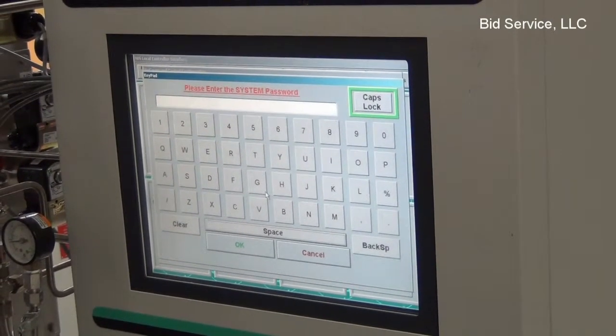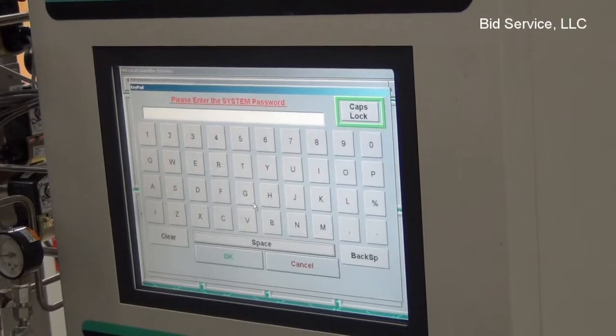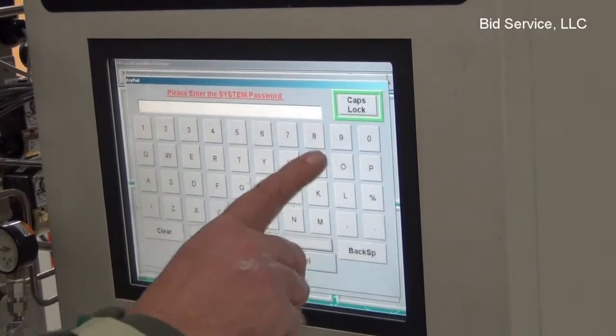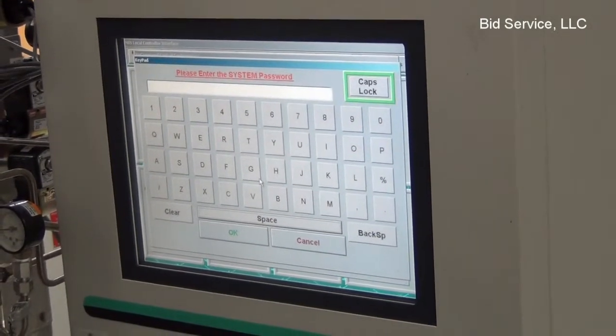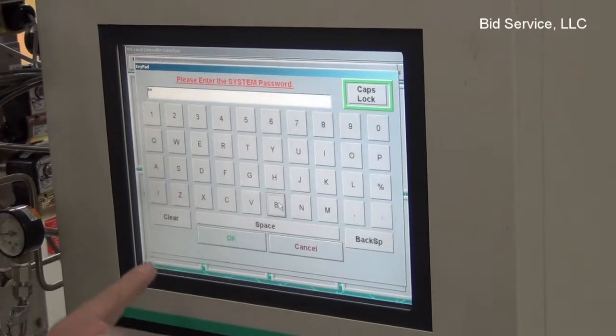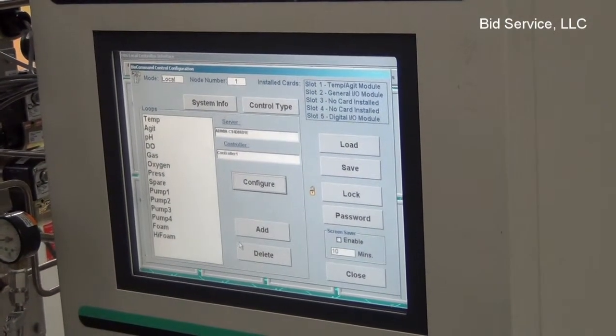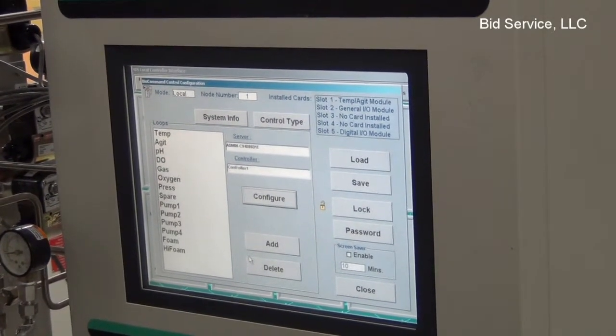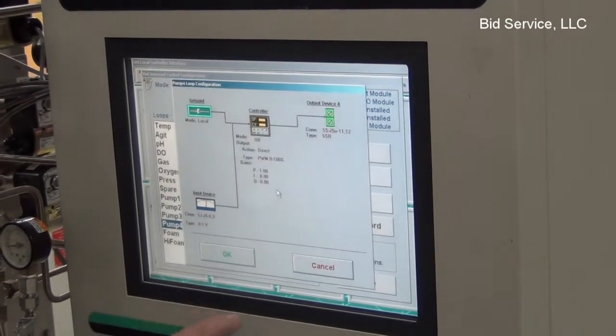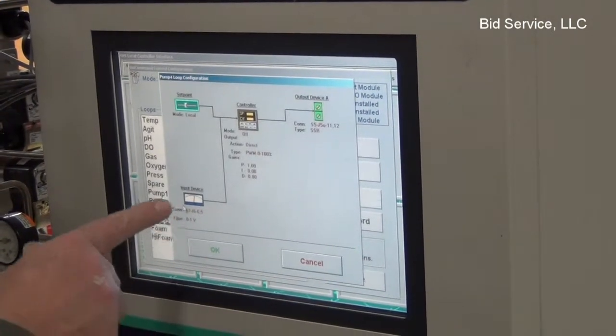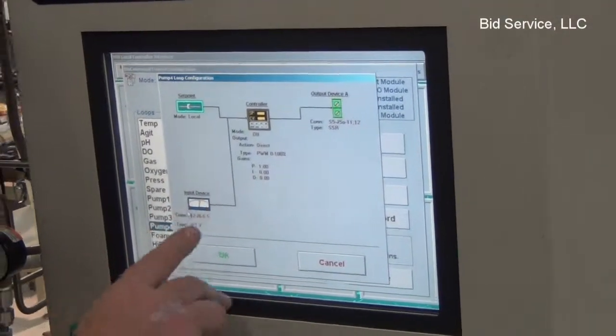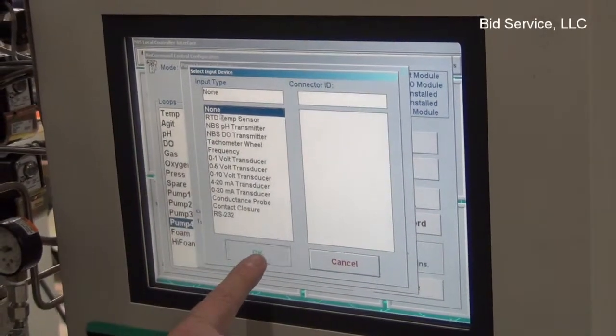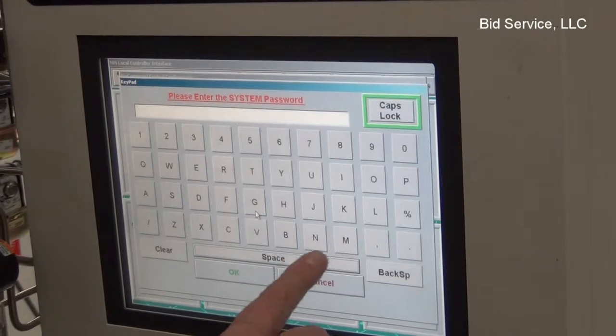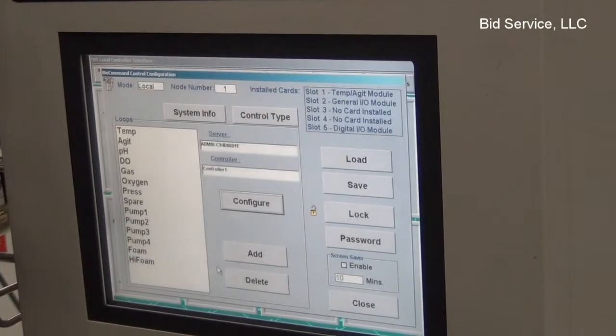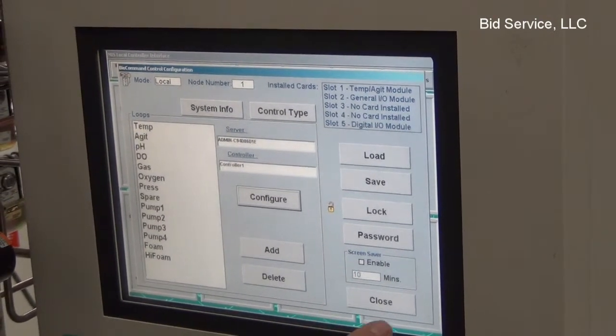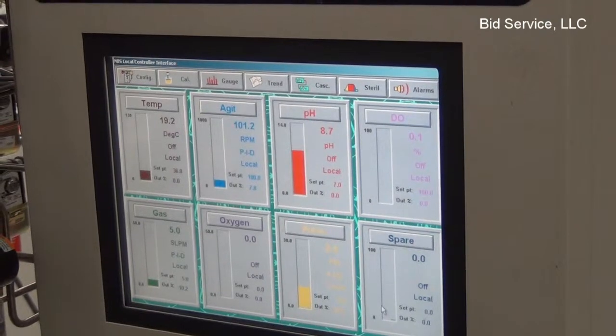And it asks you for a system password. The system password for these systems is N as in Nancy, B as in boy, S as in Sam, all capitals. This does come up and show you caps lock is on by default, so I can just hit N, B, S, and say OK, and it's accepted the configuration. So whenever you see a system password, that's it. I'm going to take that back out. Before I do that, you can just see everything I put in there is now here. But we're not using that, so I'm going to take that out, put it back to none, say OK, change it again, N, B, S, OK. At this point I can say close. And we're back to our main gauge screen.